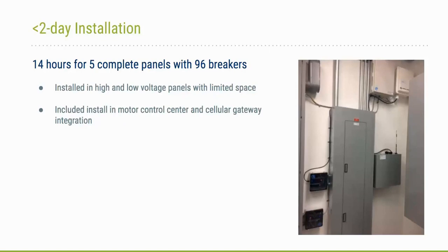You can see between the submetering panel and the existing electrical panel, there are little pieces of conduit where the CT wires and the voltage tap run. So, this obviously takes a professional electrician to do this work. They have to open the panel cover to clip the CTs around the wires. We didn't have to de-energize any systems during this install.